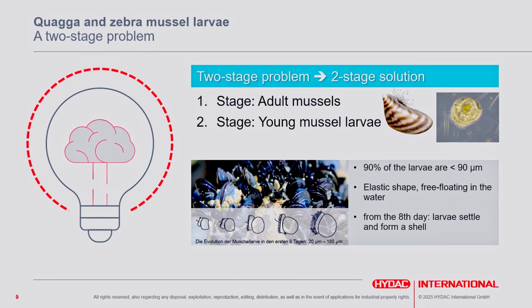The second stage is more mid-term, not immediate: the young mussel larvae. The larvae, when they enter the system, settle in the pipe from the 8th day on. When born, the larva is free-floating and elastic, goes with the flow, and may enter the system. From some point on, it builds the typical shell and they start to build colonies in the piping system. So we have a two-stage problem: one immediate problem, the shells, and one mid-term problem, the larvae.